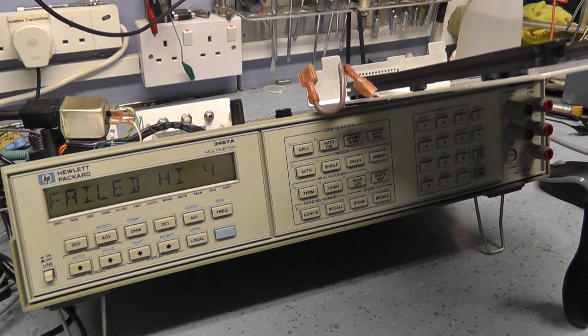use an insulated adjustment tool. Adjust C332 gain flatness adjustment until the reading indicates past 0. Ooh, this is exciting. Okay, so it's reading high. That's interesting. Let's get our twiddler in here. Oh, I do like a bit of twiddling in things like this. It's never quite the same with software control, but if you've got something you can actually twiddle inside, it's great. So let's get inside and bring this down to 0.